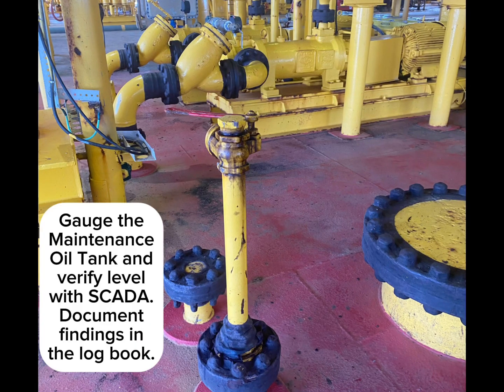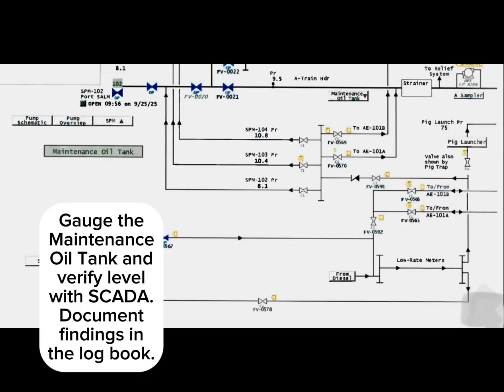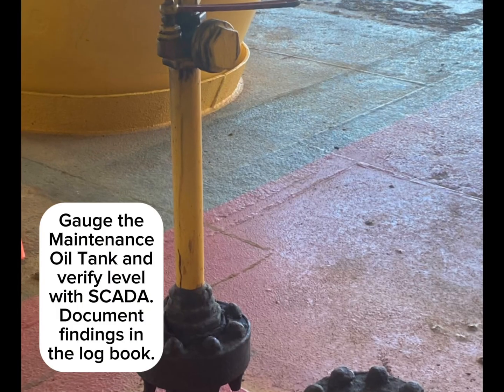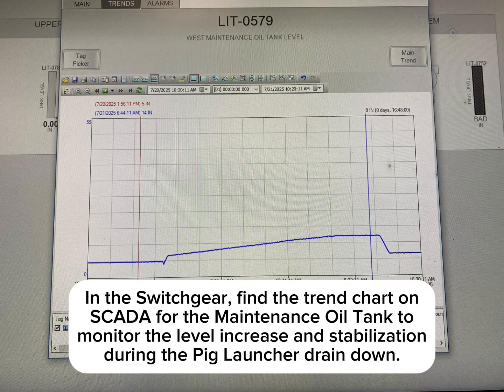Gauge the maintenance oil tank and verify level with SCADA. Document findings in the logbook. In the switchgear, find the trend chart on SCADA for the maintenance oil tank to monitor the level increase and stabilization during the pig launcher drain down.